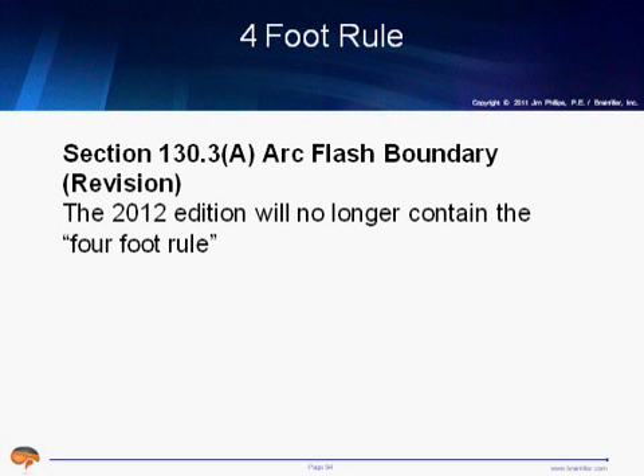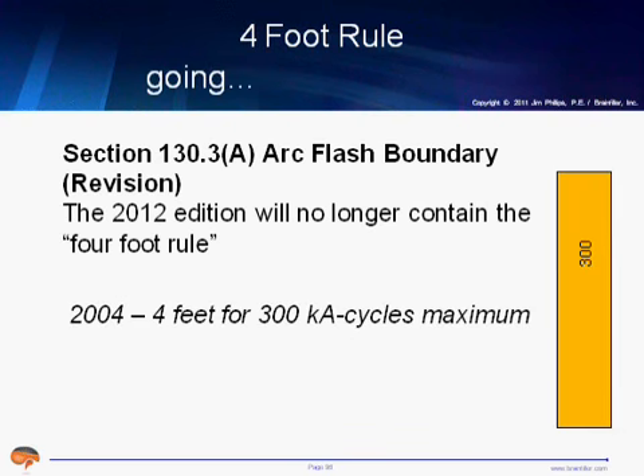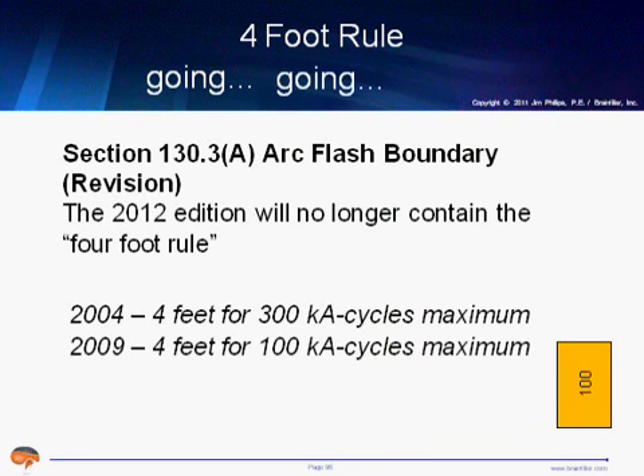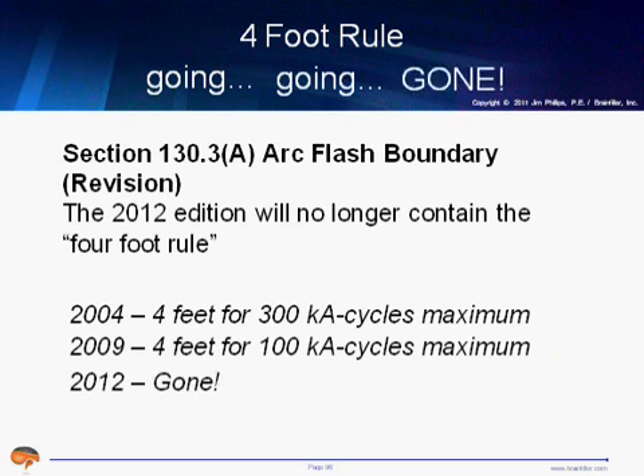Another big change within NFPA 70E is that of the 4-foot rule. The 4-foot rule in the past has been a simplified approach to define the arc flash boundary. And beginning with the 2012 edition, the 4-foot rule is going to go away. In fact, in 2004, the 4-foot rule was applicable if you had a short circuit current and clearing time up to 300 kiloamp cycles. And then with the 2009 edition, that was reduced. You could still use the 4-foot rule up to 100,000 amp cycles. And then in 2012, it's gone.